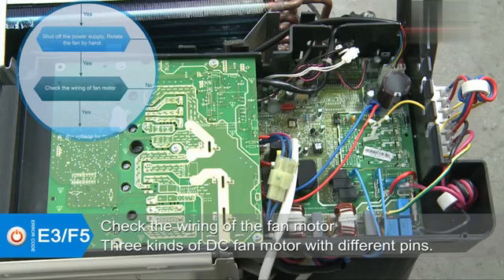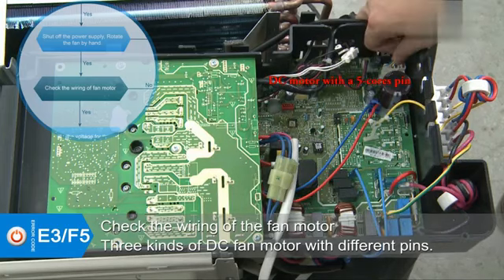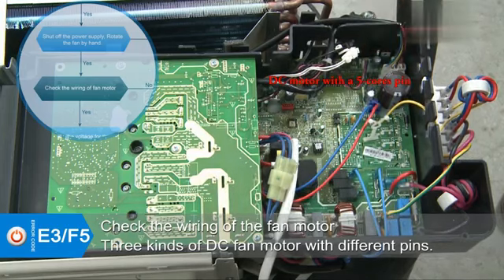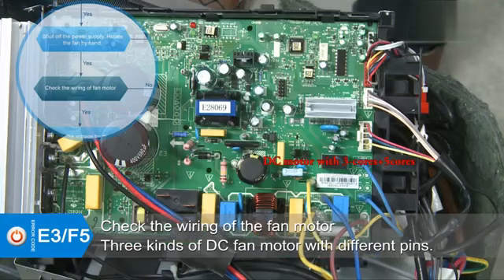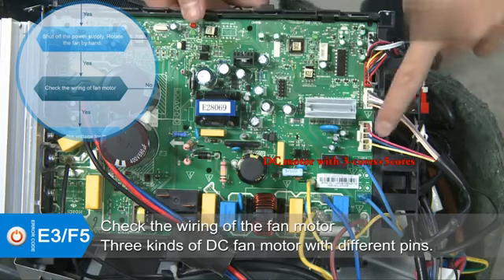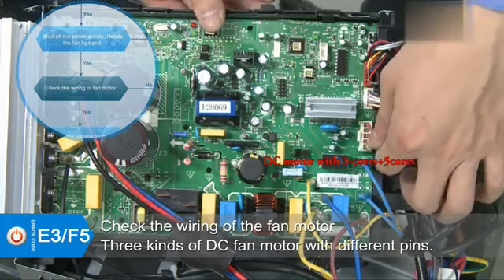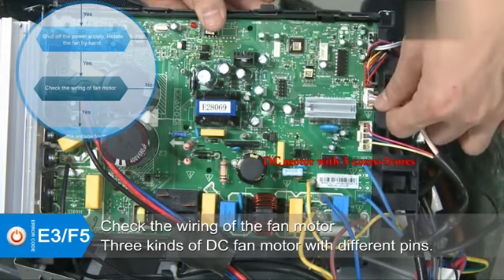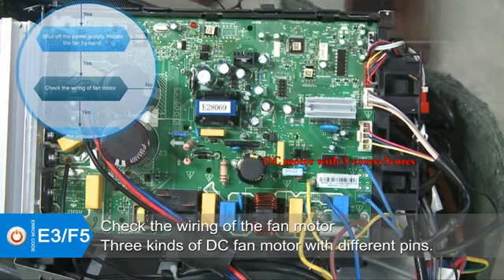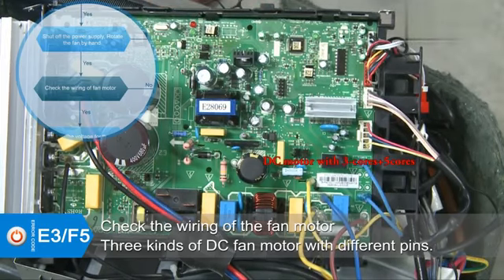Commonly, there are 3 kinds of DC fan motors with different pins. First, DC motor with a 5 cores pin, which has a control chip inside itself. Second, DC motor with 2 pins, a 3 cores pin and a 5 cores pin. The control chip for it is on the main PCB board. Separately, the 3 cores pin connects to the power supply, and the 5 cores pin is used for signal transmission.